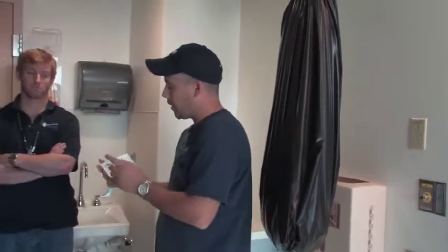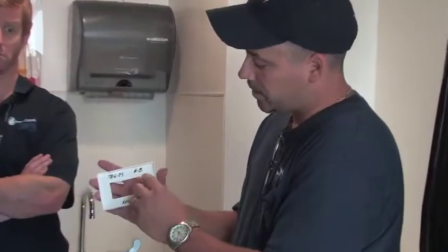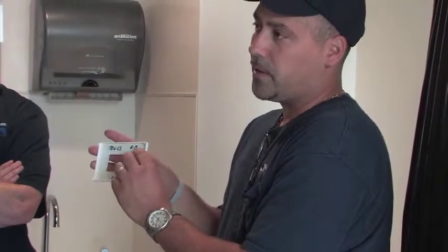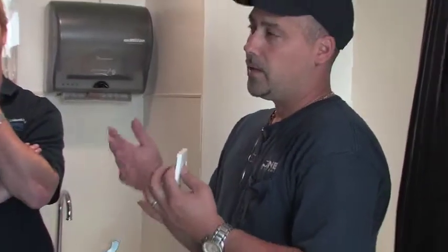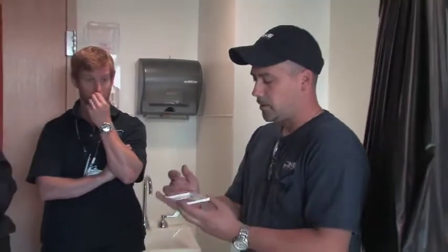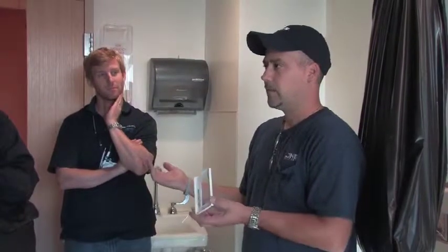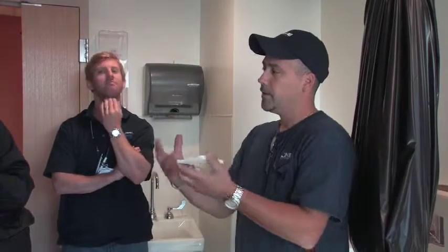And you'll notice on the bottom of all the boxes, they all say the same thing. You'll see something that says RB, RA, or RC, and those are the routers. Each floor has 3 separate routers, the iLon 600 routers, and everything has less than 30 devices on each router to keep everything at a minimum. If you're plugged into an RC controller and you're trying to see an RB, you're not going to see it. You'll have to move to an RB or an RA, unless you do the global thing where you can see everything.